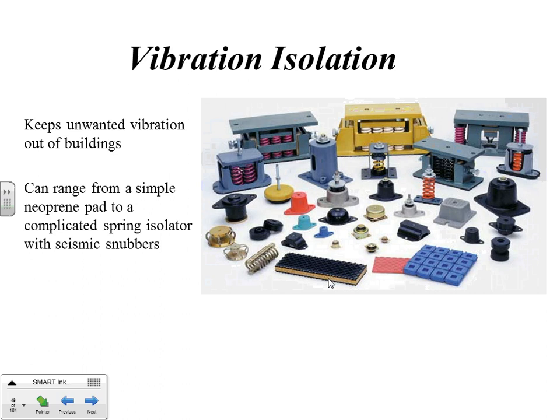These eliminate the vibration between the engine generator skid and the structure that it's sitting in. And it's of most concern inside a building. Although in big generator set enclosures, we put spring isolators in as well, because we isolate between the generator skid and the fuel tank that it's usually sitting on. Lots of different kinds. And some of these isolators, like this one in the back, it's got an adjustment screw on the side. That's for earthquake zones. So they've got what they call seismic isolators as well.